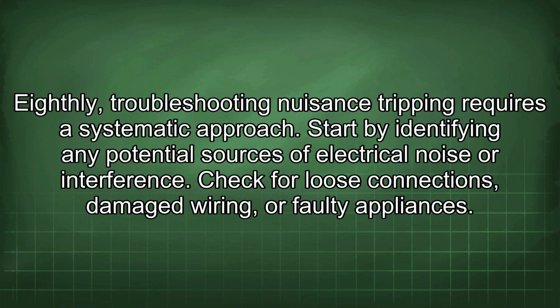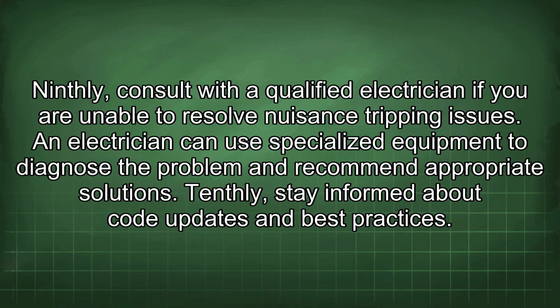Eighthly, troubleshooting nuisance tripping requires a systematic approach. Start by identifying any potential sources of electrical noise or interference. Check for loose connections, damaged wiring, or faulty appliances. Ninthly, consult with a qualified electrician if you are unable to resolve nuisance tripping issues. An electrician can use specialized equipment to diagnose the problem and recommend appropriate solutions.